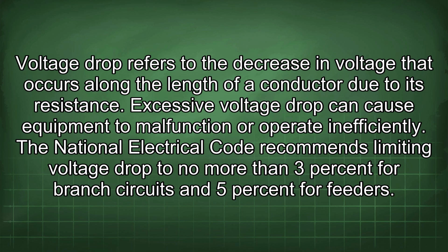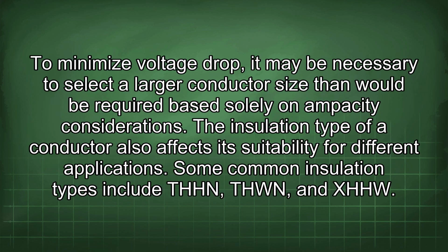The National Electrical Code recommends limiting voltage drop to no more than 3% for branch circuits and 5% for feeders. To minimize voltage drop, it may be necessary to select a larger conductor size than would be required based solely on ampacity considerations. The insulation type of a conductor also affects its suitability for different applications.